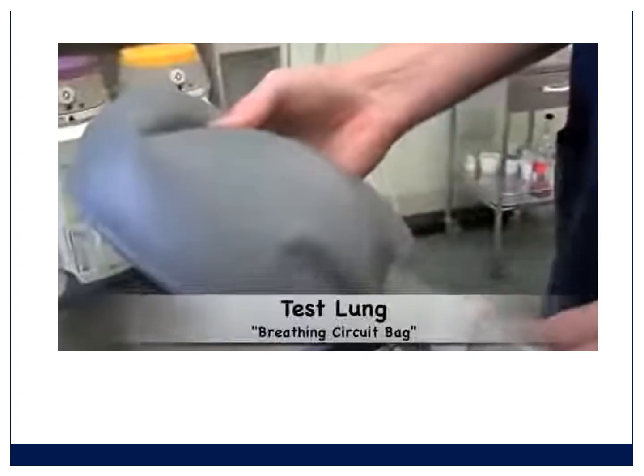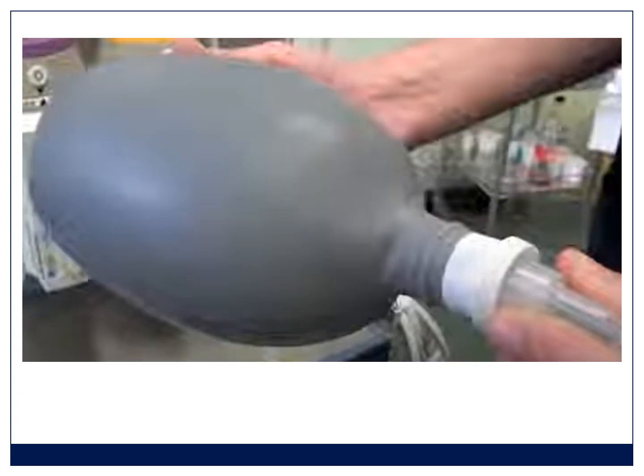Then you want to attach a test lung, and a test lung is just another bag that you stick on the Y piece. So you put the bag on the Y piece, you close the APL valve, turn up the air oxygen rotameters, and you make sure that you can pressurize the system. Then you turn on the ventilator and you ventilate in the mode that you want. So put it on volume control, once that circuit is pressurized, you should be able to turn the gases right down to minimal flows, and then you ventilate with the mode that you're going to use on the patient.